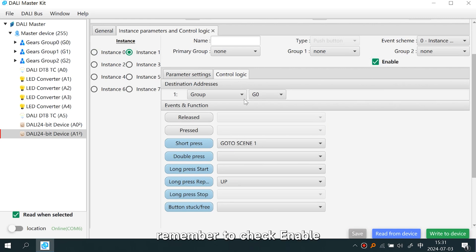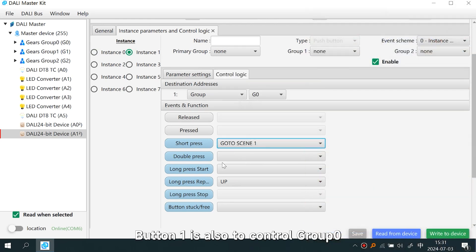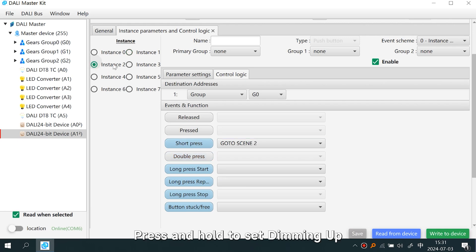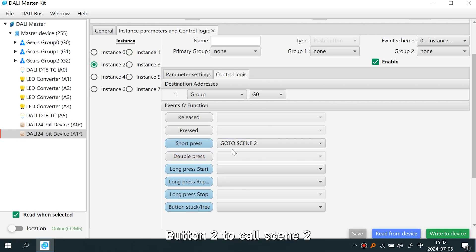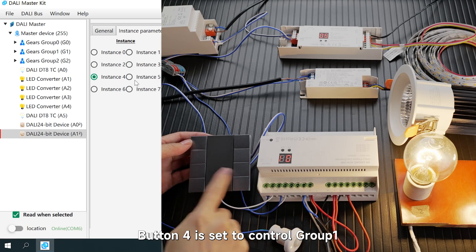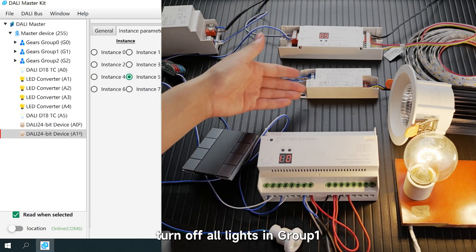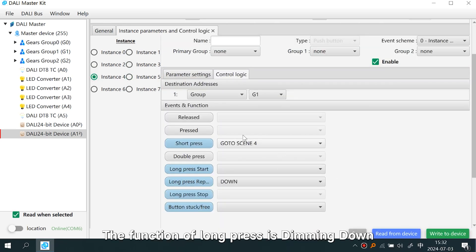Next, set Button One — remember to check Enable. Button One also controls Group Zero: short press calls Scene One to turn on all the lights, and press and hold to set dimming up. Button Two calls Scene Two. Button Three calls Scene Three. Button Four is set to control Group One, calling Scene Four to turn off all lights in Group One, with long press set to dimming down.